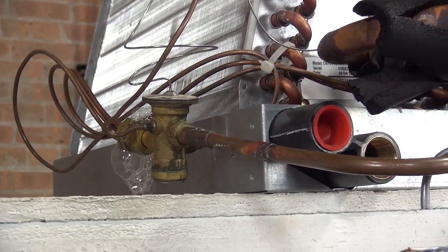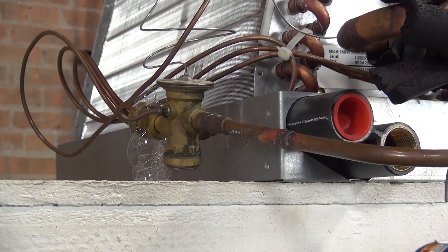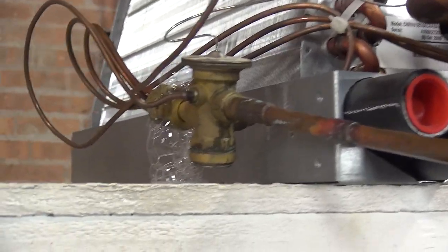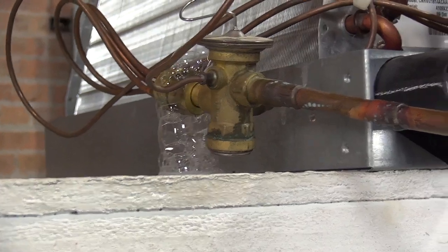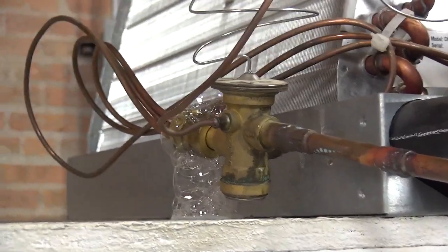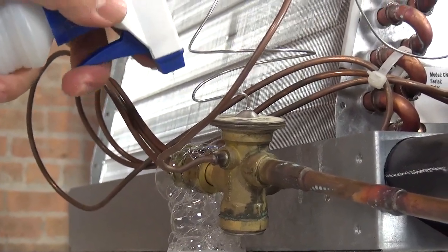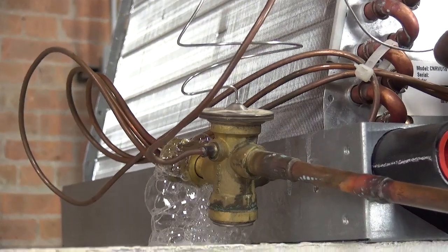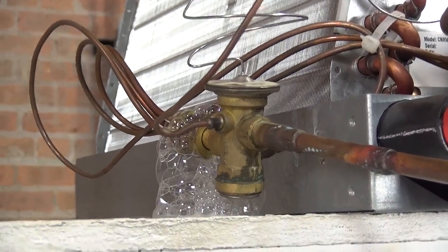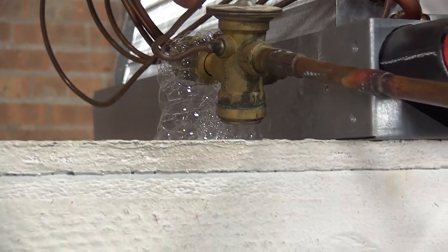And by the way, you know that this is not gonna happen in the field that easy. I'm just showing you what happens once you apply the nitrogen, and you get the solution, and look at that bubble. And that's a leak. That's how you find leaks. Okay? In this case, we have two connections that are loose.